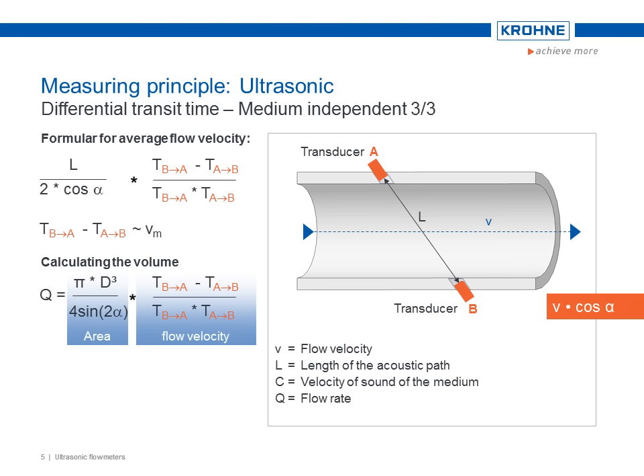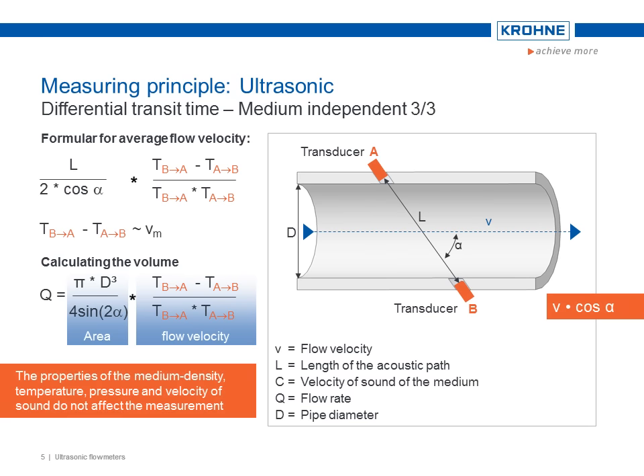The cross section of the pipe is constant for an inline ultrasonic flow meter with a diameter D and transducers which are welded into the spool piece at a fixed angle alpha. These formulas confirm what we have already seen, that is, that the characteristics of the medium do not affect the measurement. These characteristics include density, temperature, pressure, and the velocity of sound of the medium.